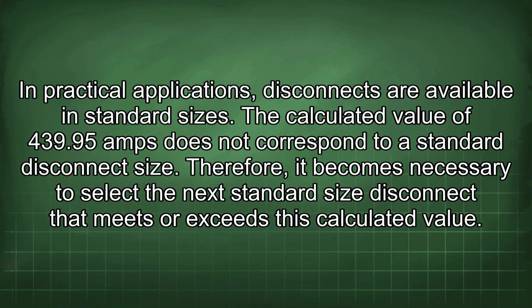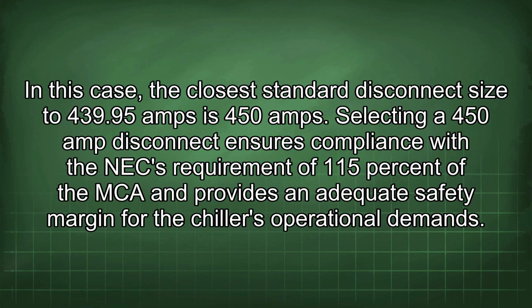In practical applications, disconnects are available in standard sizes. The calculated value of 439.95 amps does not correspond to a standard disconnect size. Therefore, it becomes necessary to select the next standard size disconnect that meets or exceeds this calculated value. In this case, the closest standard disconnect size to 439.95 amps is 450 amps. Selecting a 450 amp disconnect ensures compliance with the NEC requirement of 115% of the MCA and provides an adequate safety margin for the chiller's operational demands.